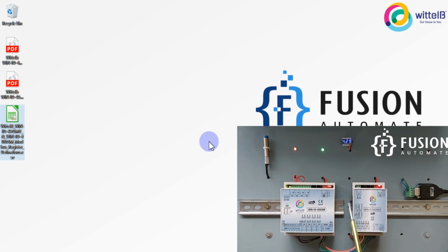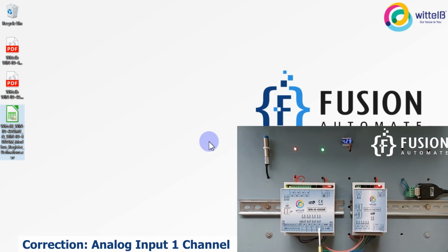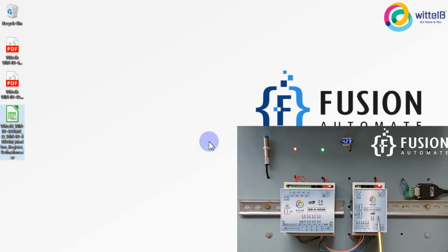I have connected these two LEDs with DO1 and DO2. I have connected this sensor with DI1. I have connected this DC voltmeter with analog output 1, and I have connected the analog output 2 channel with the analog input 1 channel. So now in this video we will see how we can test these two Modbus IO cards, or how we can troubleshoot these two Modbus IO cards.